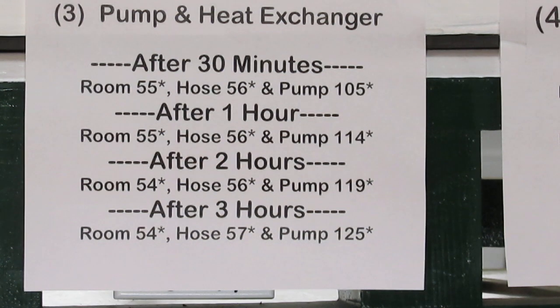So what can we learn from test 3? The heat exchanger did a very good job of reducing the hose temp by itself, but didn't get the hose temp down to the level of the room temperature. Most of the time, the water temp will be lower than the room temperature.